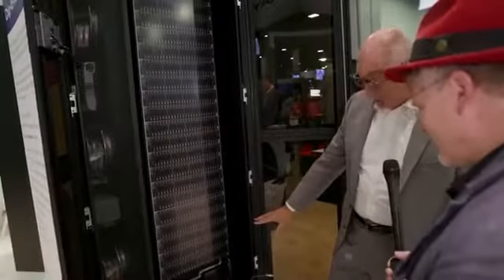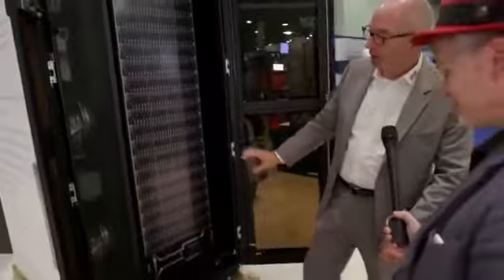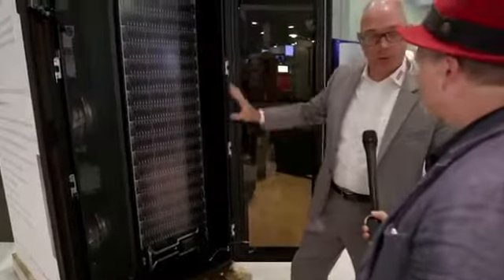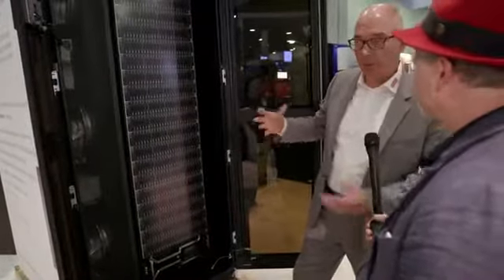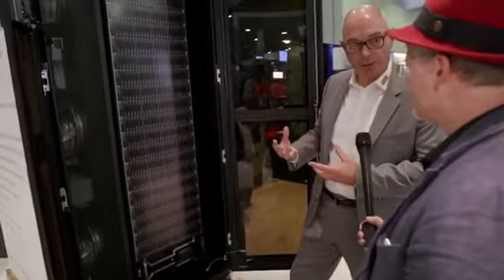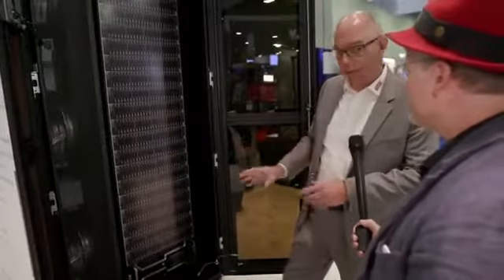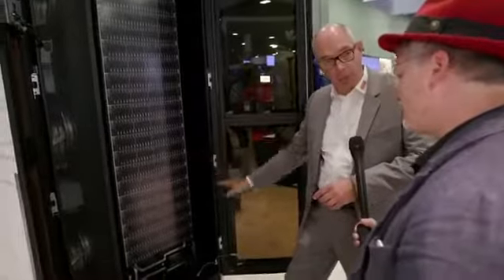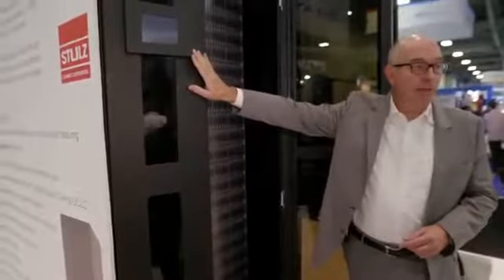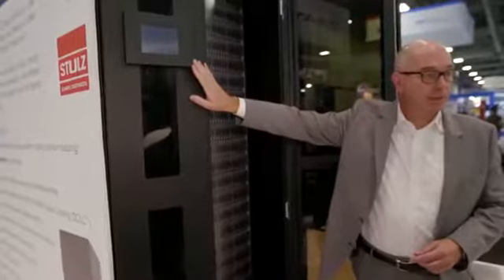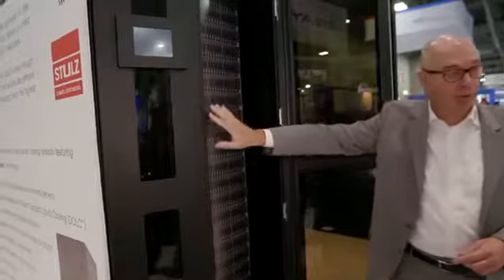Then on the bottom we have the CDU. The key element here is that each of these components have controls, so we wanted to make sure we integrate the controls to a level that a customer does not need to deal with controlling a liquid circuit from CoolIT and an air-cooled circuit from STULZ separately. We wanted to combine everything into a single control element and an interface at the front of this rack to control both circuits.